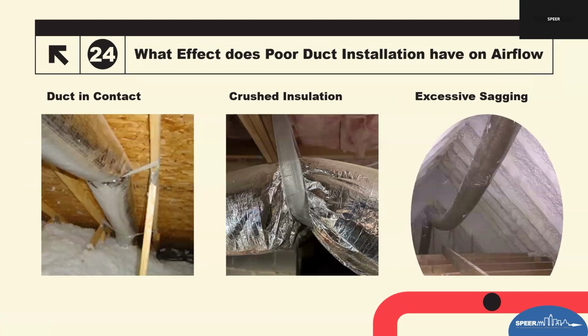And then what effects does the poor installation have for airflow? We talked about that just a second ago. First of all, I want to point out the one that's on the far left is a blown attic. I get it. But this is a good example of we shouldn't see this in a blown insulated attic anyways. It should not have a duct in contact with the roofing deck, period. I don't know how you cut it other than the fact that you just don't leave it in contact. But if we're looking at a foamed house, we should definitely not see that because now it's outside the conditioned space. And then crushing the outer insulation with the straps. Most cities don't require saddles. I hope one day that that's in the code.